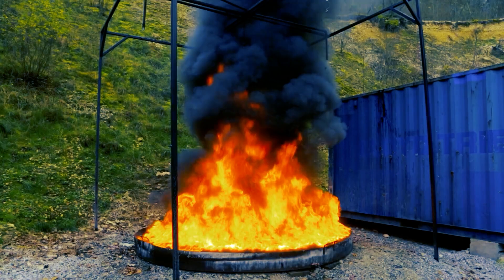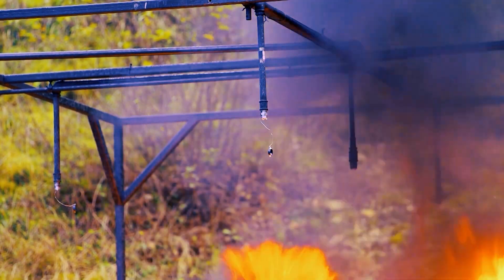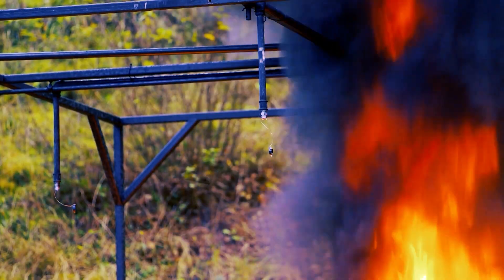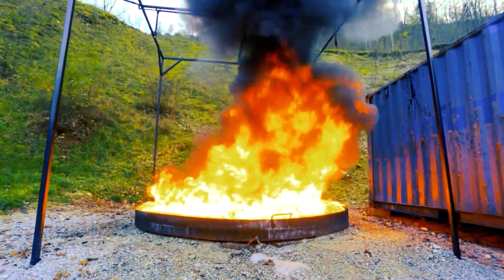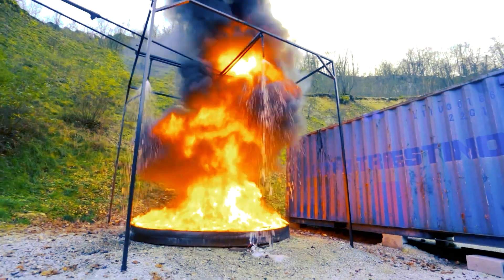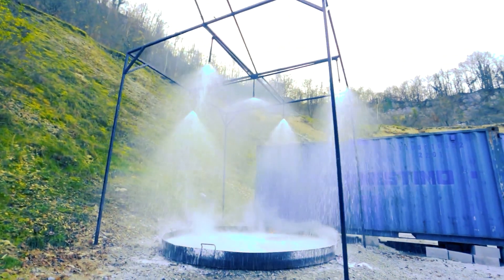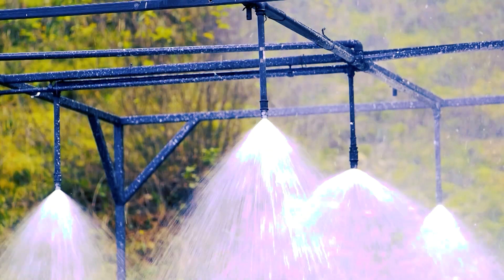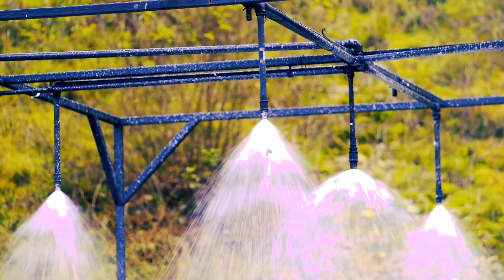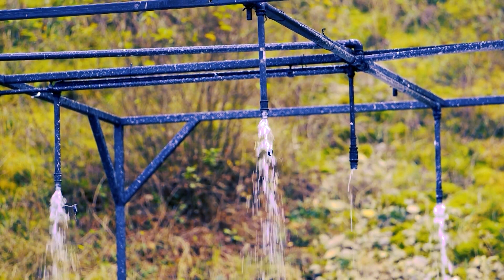Bonpet Fix fire safety system is designed to be a zonal fixed extinguishing system for use in both closed and open spaces with no other limitations. It can be activated automatically or manually. The fire detection and extinguishing process does not take more than 90 seconds from the moment the fire breaks out. The extinguishing is not dependent on electrical power and does not cause additional damage to the environment, unlike foam, powder, or harmful gases.